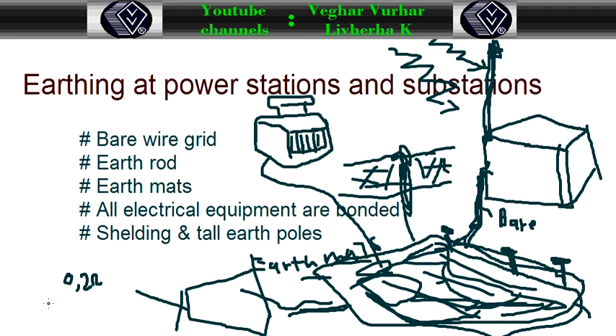When testing the earth, it must give you 0.2 ohms to be safe, because this shows that the resistance allows current to pass through here simply and then go to ground. The current chooses the lowest resistance to go through. If there's a lower resistance, it will take that path. If you have a 10 kilo-ohm, it will take this one before that one. Make sure that the earth mat is close to 0.2 ohm. Some prefer maybe 0.5 - between these two is safe for this substation.